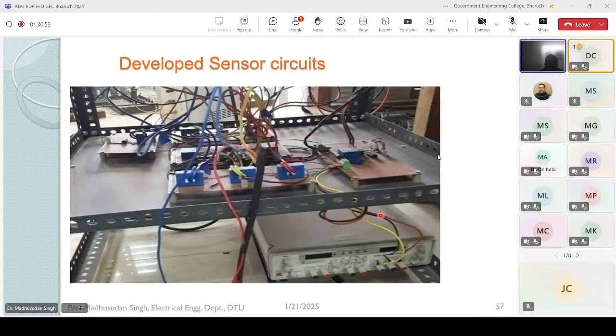These are the isolator circuits. This is a very popular and commonly used IC for opto isolators, which are used in the driver circuit. The signals coming from the dSPACE are not directly applied to the inverters; isolation is desired. There are 6 signals, so 6 such parallel arrangements are made, which is known as a driver. The driver is an electronic circuit which converts a low 5 volt signal to a 15 volt signal required to run the IGBT, and it also has its own separate ground. You see, this side's ground is different from that side; there is no common ground.